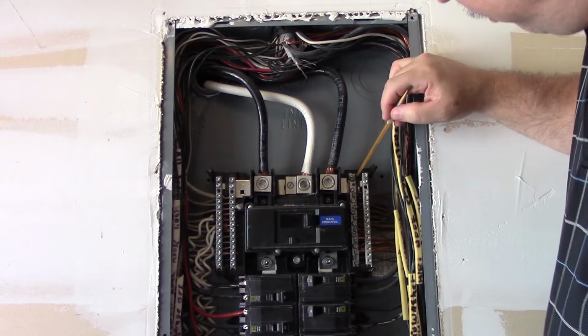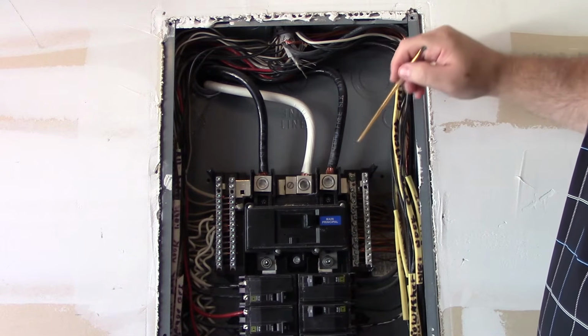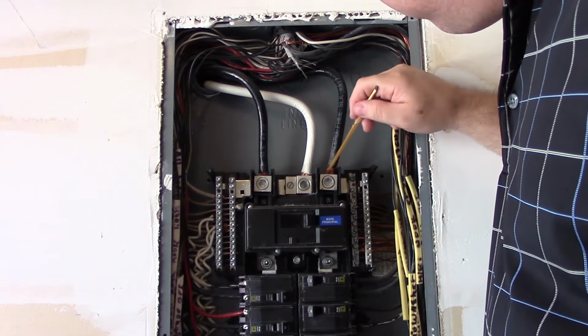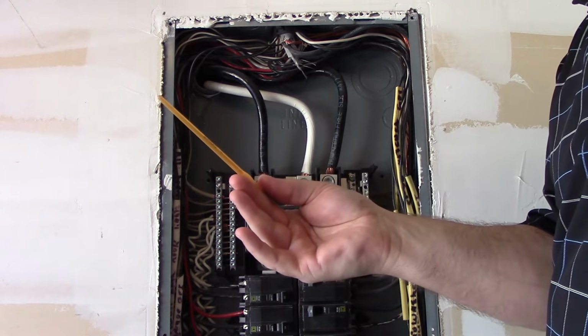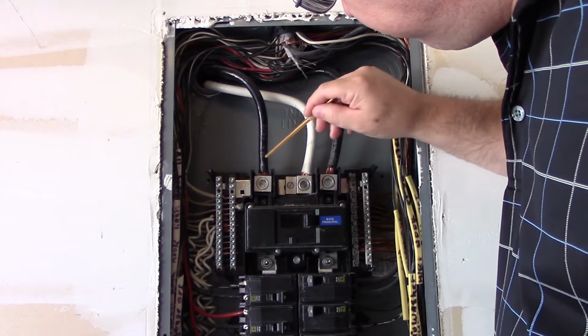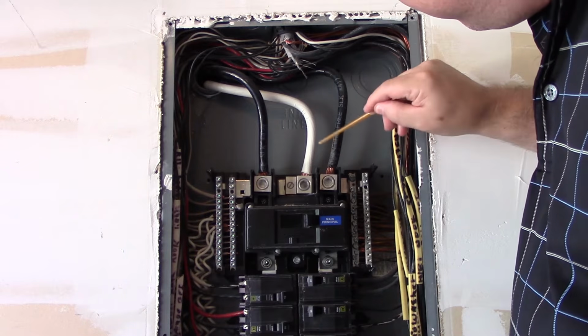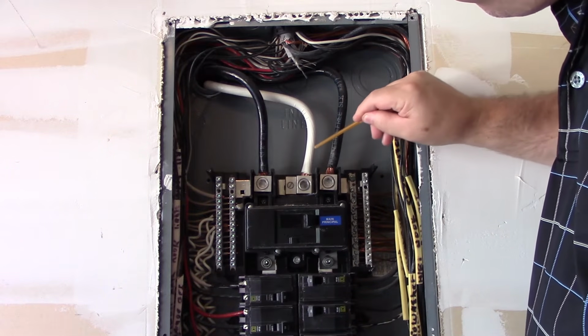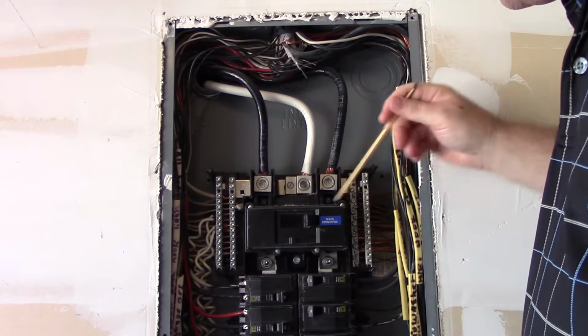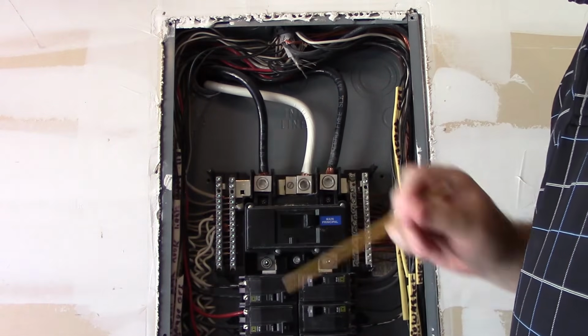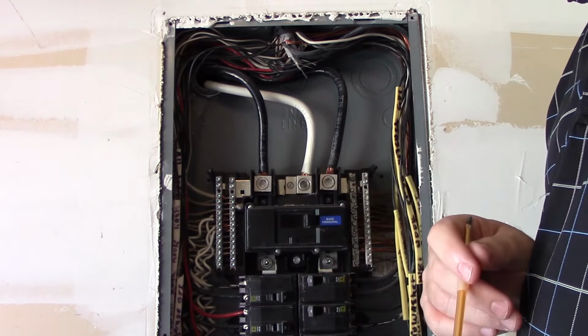All right, so one thing we notice here as we're going around looking, everything looks good. The terminals look all right. There's no deterioration here, no discoloration. Again, non-conductive probe. I'm looking in here. Everything looks pretty good. Everything's tight. Not an issue with that. Again, your standards of practice might say not to poke things into the panel. I'm a licensed master electrician.